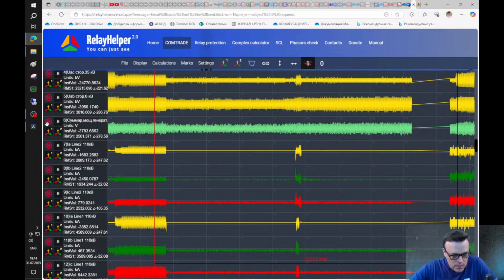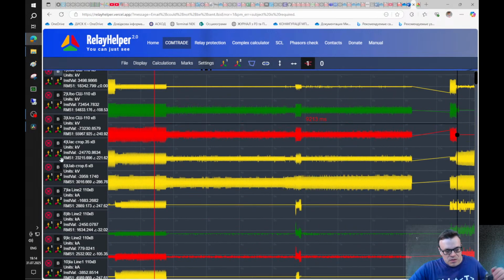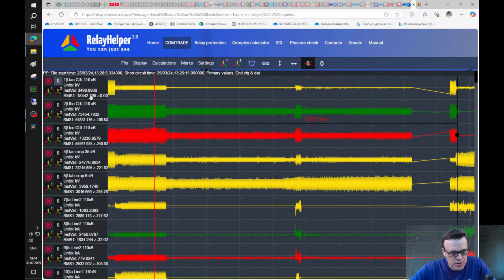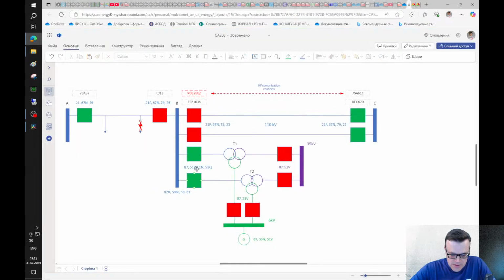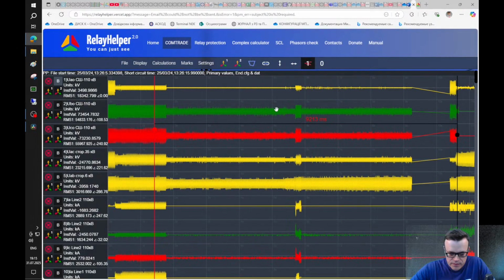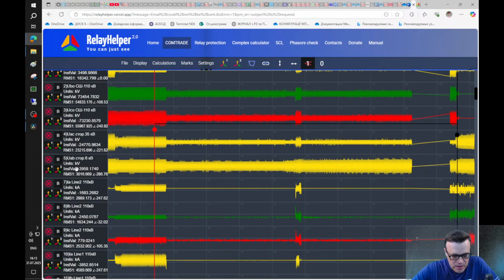I described U channels. So the 3 channels on the top are the voltages from the 110 kilovolt side. This one, 4th channel, is voltage between A and C phases from 35 kilovolt side. I remind you that we talk about this substation B and these transformers, and so this is from this side, 35 kilovolt.